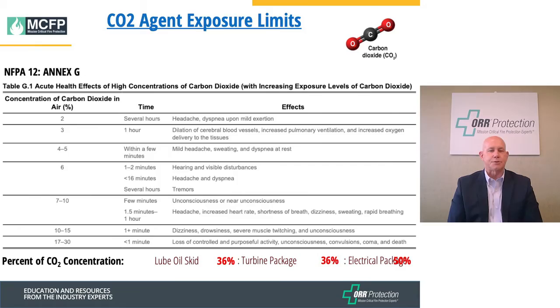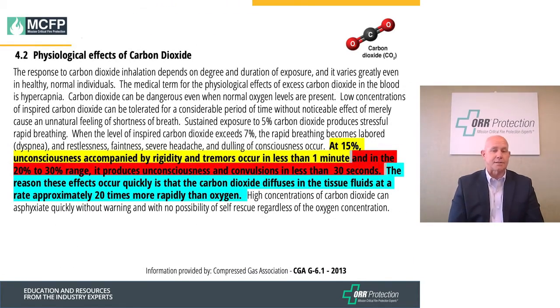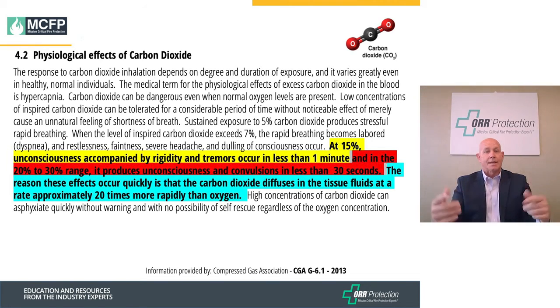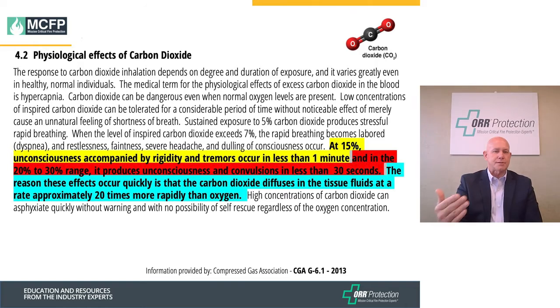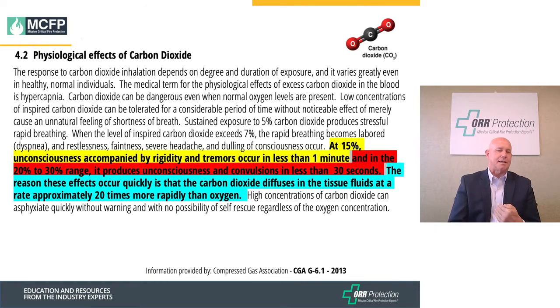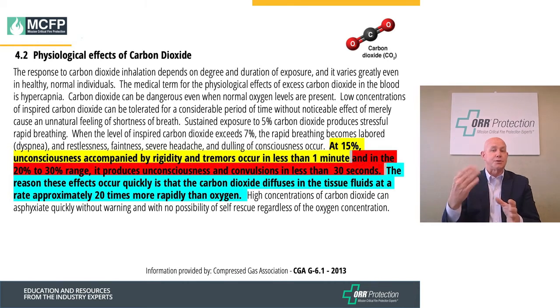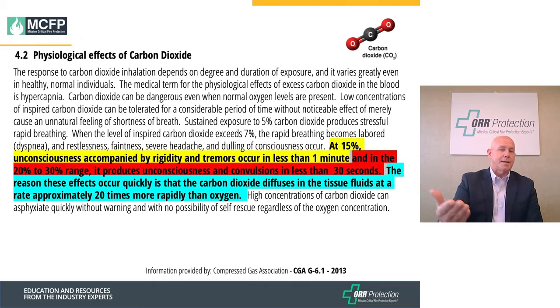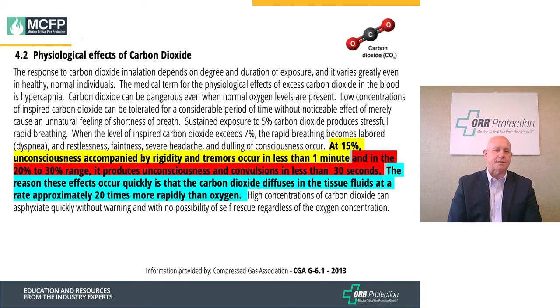This chart came from the Compressed Gas Association (CGA). What I want to highlight is that at 15 percent CO2, you start having tremors after just one minute of exposure. If we typically protect a lube oil skid at 36 percent, power generation personnel can see that only one minute of exposure creates the possibility of tremors and adverse effects. At 20 to 30 percent, you can become unconscious in only 30 seconds — so you really have to be careful.